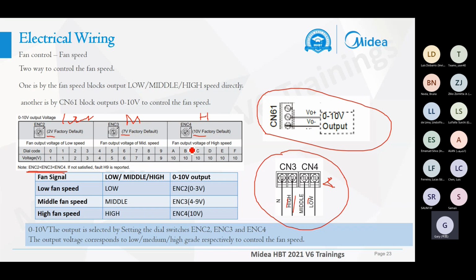You can also change this value for each speed, but you should follow these rules. The high speed should be set at 10 volt, but the middle you can set from 4 to 9 volt, and the low you can set from 1 to 3 volt. This is for the 0 to 10 volt output control. And for the CN3 and the CN4, you can connect directly for the relay of the fan speeds.